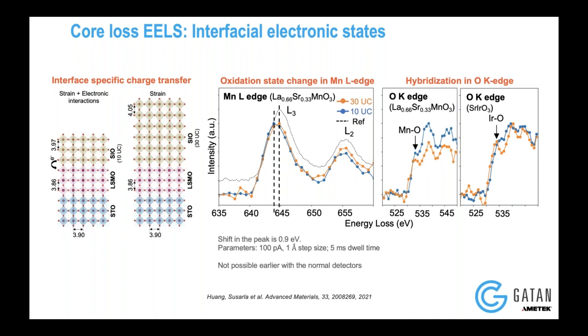All of these changes happen both on the LSMO side and the strontium iridate side. I would like to emphasize that all of these chemical maps were collected with a very small dwell time, which means we don't give enough time for the material to be damaged by the electron beam. If you increase your dwell time by a lot, you can introduce different kinds of oxygen vacancies or change the oxidation state of transition metals.